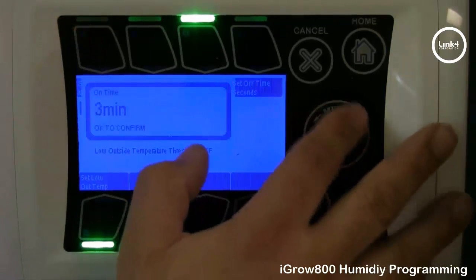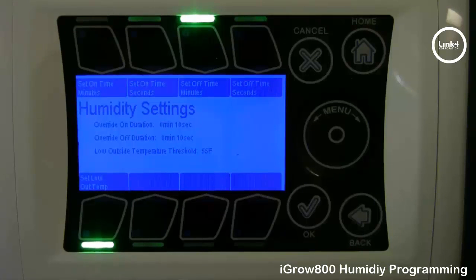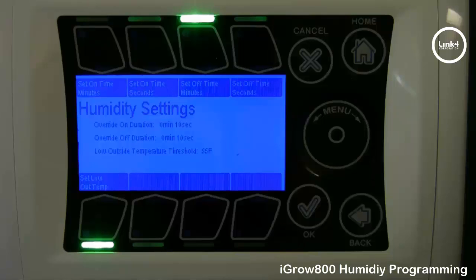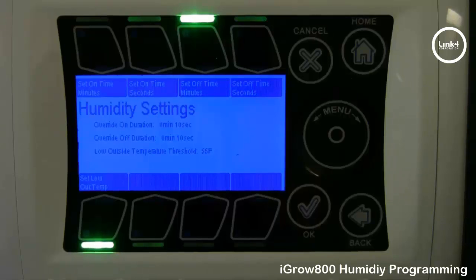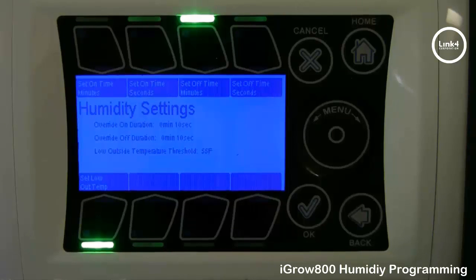The wheel allows you to increase and decrease your values. The override on duration is the time for the override to remain active, and the override off duration is the time for the override to remain inactive or off. This allows fans, dehumidifiers, heaters, and misters, for example, to turn on and off to help get the relative humidity within its set points. For vents and curtains, this feature will open and close to a predetermined percentage. For example, if the controller goes into a dehumidification state and is in cool stage one at 25%, but then goes into dehum mode at 50%, the vent will cycle open to 50% for the override on duration, and then close back to 25% for the override off duration. On the other hand, if the controller is in cool stage five at 75% but goes into dehumidification mode at 50%, the vent will remain at 75% due to it being a greater value than the dehumidification percentage value.